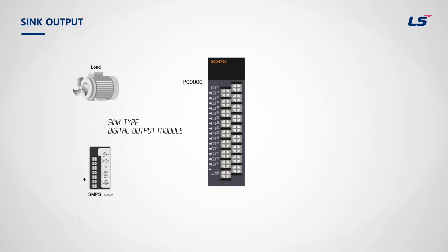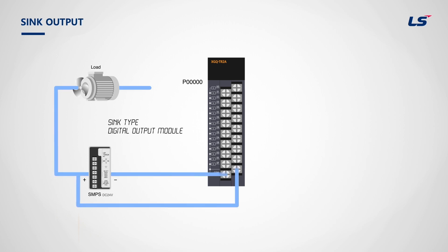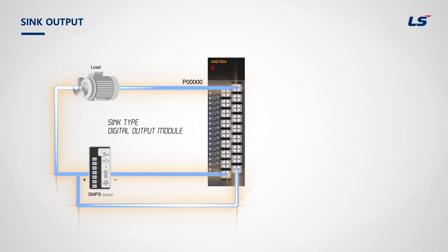This is the sink type output module. For the sink type output module, the COM terminal of the PLC output module is connected to DC 0 volts power source. The only difference between the sink type output module and input module is that the output module needs a jumper. The positive terminal is connected to 24 voltage, just like shown in this video.